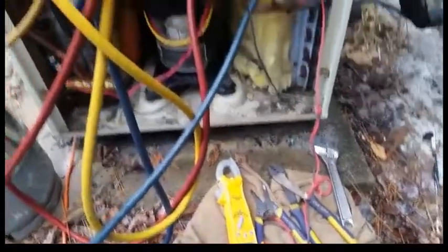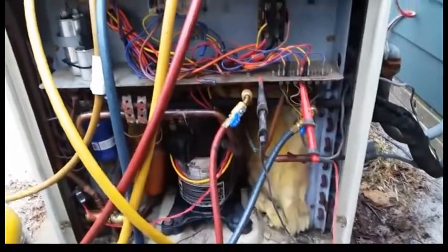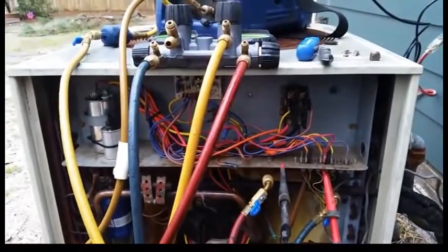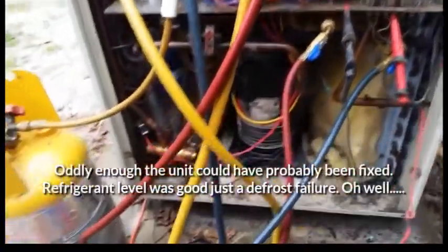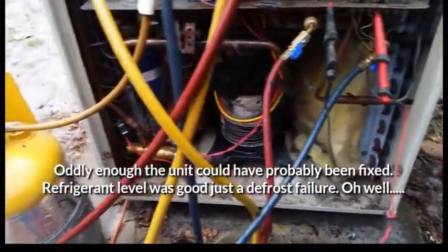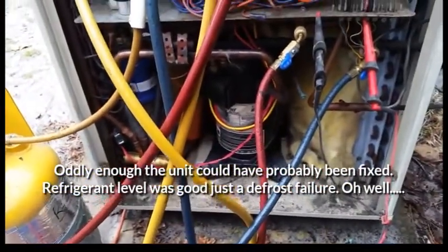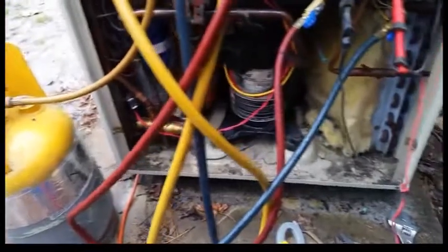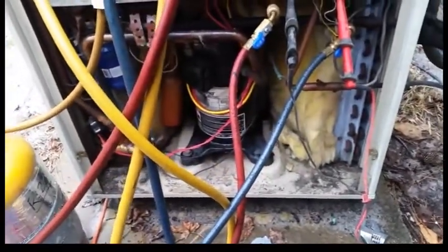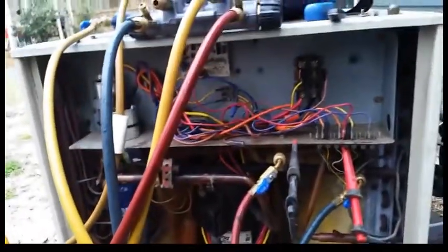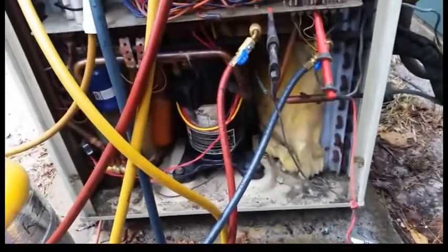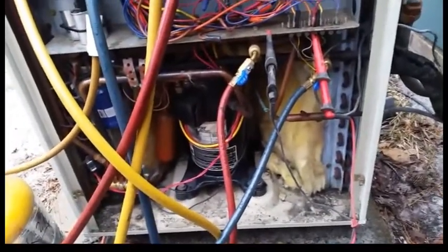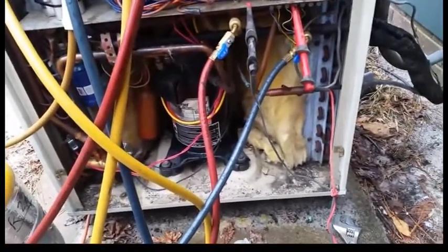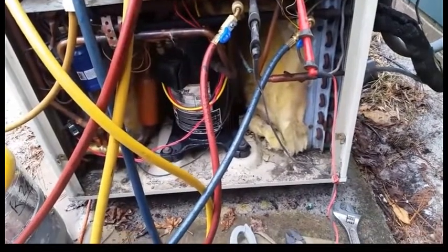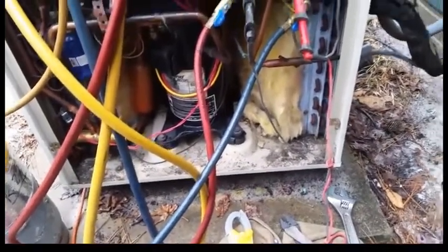Hey guys, I'm taking this old Lennox out here. Kept frosting up, and the homeowner said it was just time to take it out. Looks like some bad placement on the defrost sensor, kind of catching it on the tail end there, maybe not defrosting as often as it should. That's hard to tell, it's been doctored a little bit here, but she's going bye-bye. To be replaced by a Payne matched with a Carrier indoor unit, because they're basically all made by Carrier.